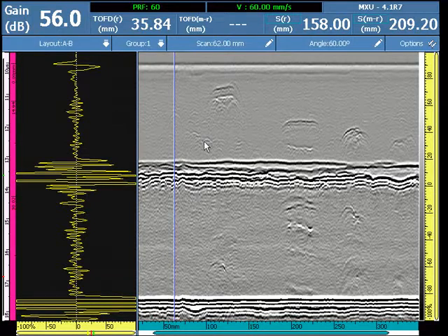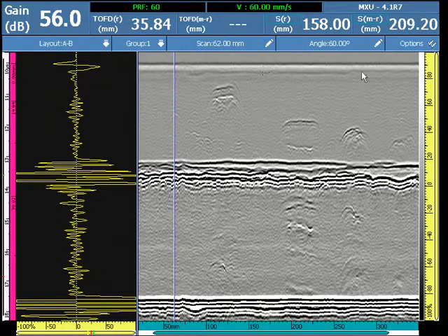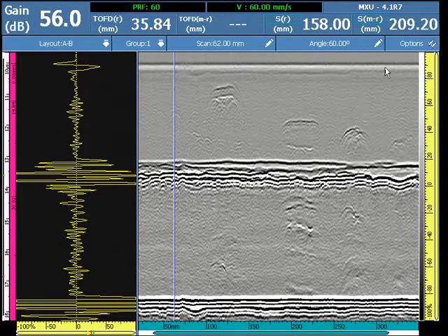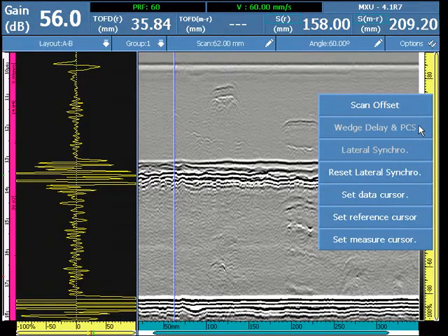OmniScan flaw analysis and characterization of TOFD indications is carried out in full screen mode using the A and B scan layouts. Prior to analysis, the file would have been straightened for the lateral wave, and during that we'll make sure that there are no defects in or around the lateral wave prior to straightening, so that they're not masked. The calibration was performed using a wedge delay and PCS.